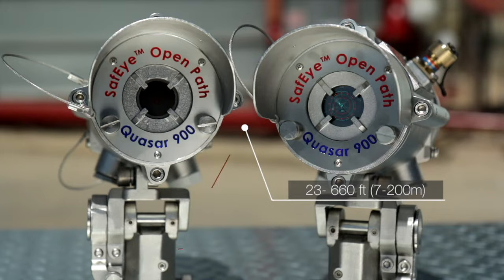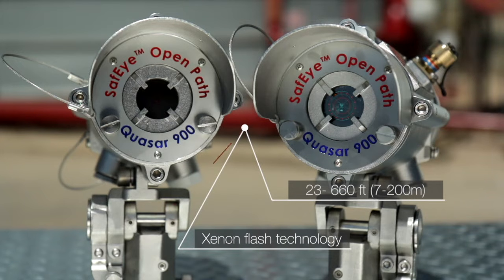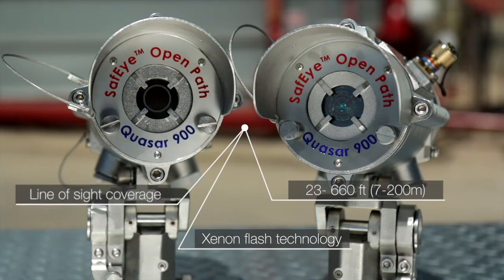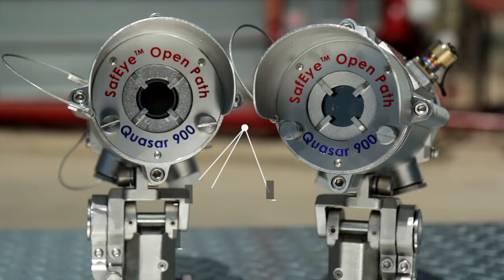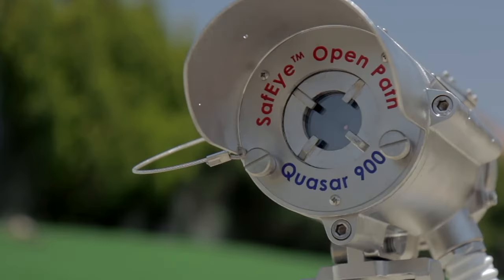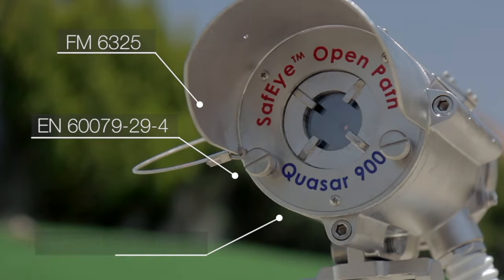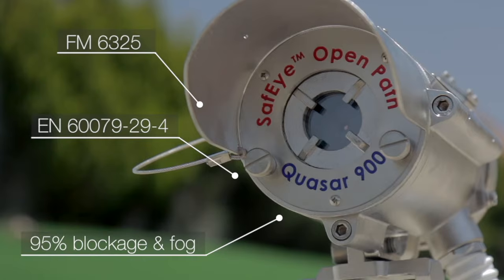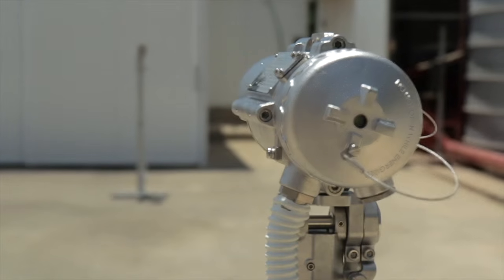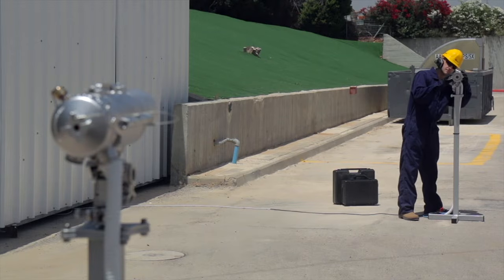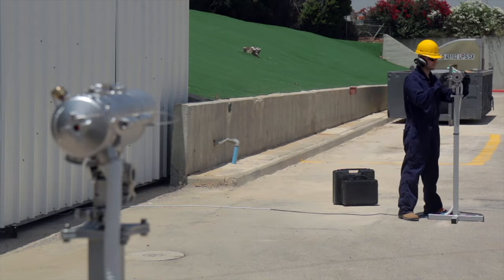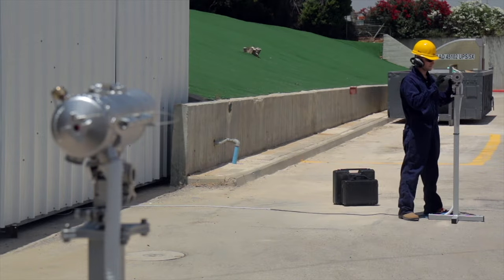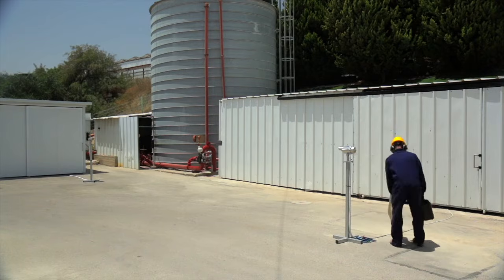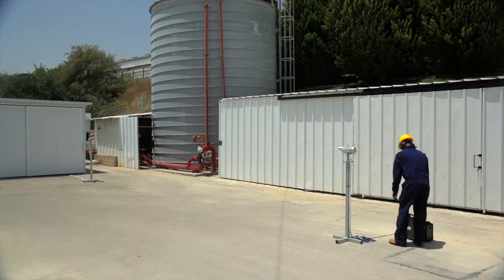It has been designed to operate in extremely harsh environments where dust, fog, rain, snow, or vibration can cause a high reduction of signal. It is certified by FM 6325, which includes operation at 95% signal reduction and fast response time. Open path gas detection is ideally suited for applications requiring a single detector to cover a large area of potential leak sources. The Quasar 900 can be installed and maintained by a single person.